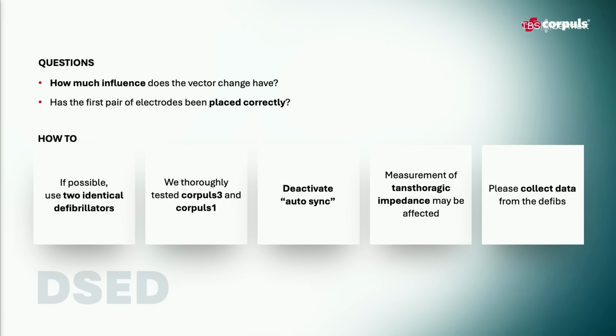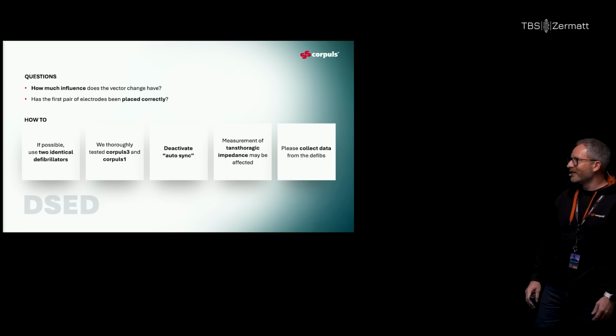You might want to consider using two identical defibrillators. As I pointed out before, there's a range of voltages. Some might use a slightly lower voltage and be insulated against that. If you combine that with one of ours, you might risk damaging the other one - which from my commercial perspective isn't that bad, since then you'd need to buy another one. But for you to keep your equipment, that's probably something to consider.